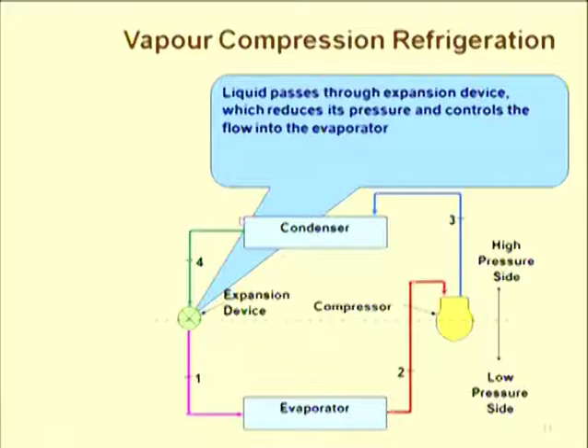That's why, as I have told you, between the condenser and the expansion device there is a receiver placed in the circuit which stores the extra refrigerant, because the expansion device is also a flow control device. It is not just expanding the gases but also controls the flow. That's why the receiver, which stores the extra refrigerant, is placed between the condenser and the expansion device, so that the expansion device can control the flow of refrigerant. The extra refrigerant can be stored in the receiver, and the rest is supplied to the evaporator, where by absorbing heat the refrigerant is evaporated and the cycle is repeated.